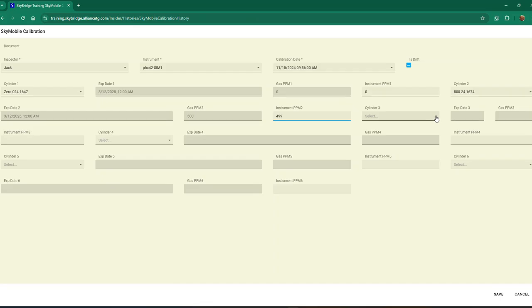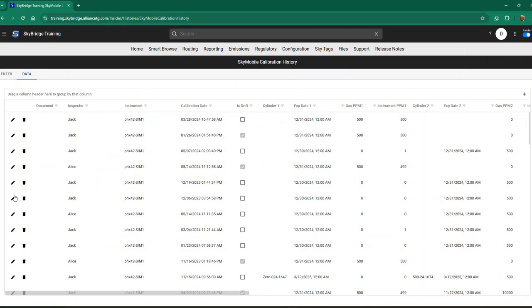Okay. Then I'll go ahead and do my next calibration gas, and that's going to be 10,000. I'm not going to do 2,000. And then it populates the information. There's the 10,000 concentration. And then whatever I got on there, I'll put in here. Okay. And once I'm done with my daily calibration, remember, I don't do anything with drift right now, right? So I go ahead and hit save here. Okay, save, right? So I'm done with my daily calibration.